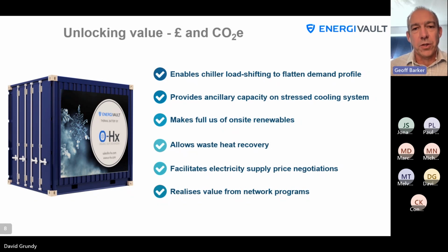So you can effectively reduce or replace that inefficient chiller capacity, and we found chillers in February, March time running with a COP much less than 2. If you can replace that with stored energy, which has been created with a COP over 3, then you're effectively roughly 50% more efficient delivering EnergiVault instead of that part-loaded chiller. If you're using 50% less energy, then correspondingly you're using less carbon, and depending on where you're taking your power from, whether it be local on-site generation or mains grid, you'll probably reduce your CO2 by at least 50% when you're replacing that chiller load.